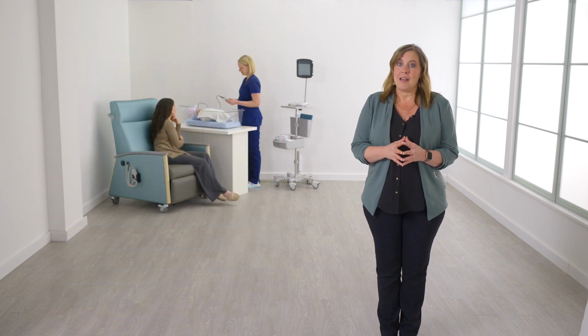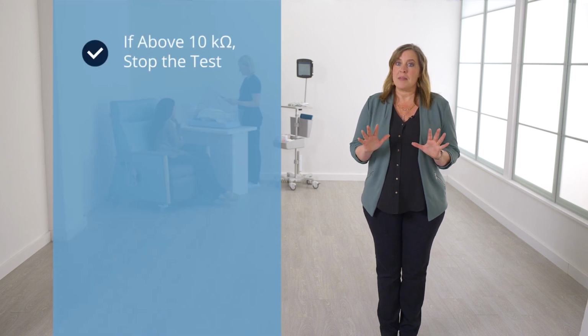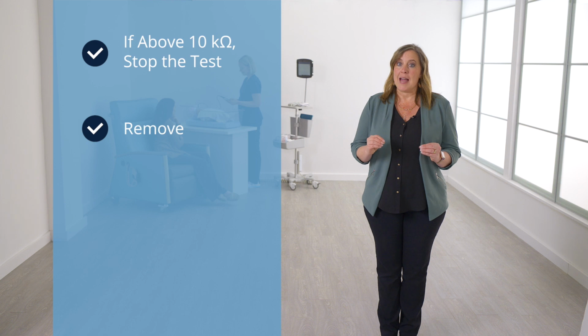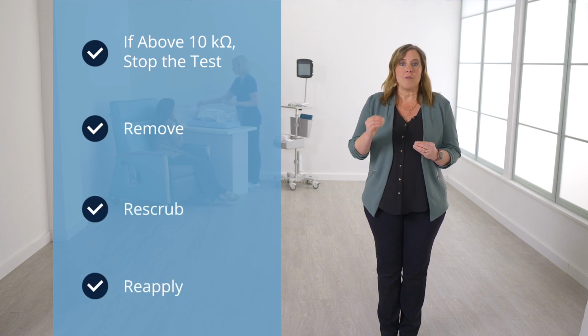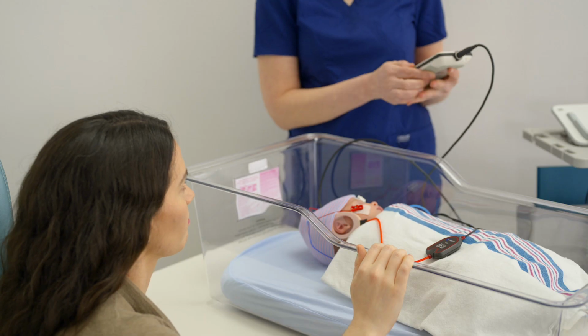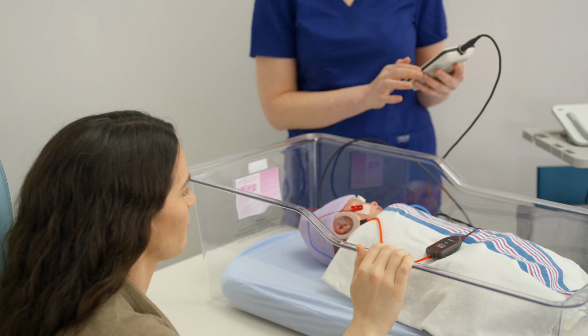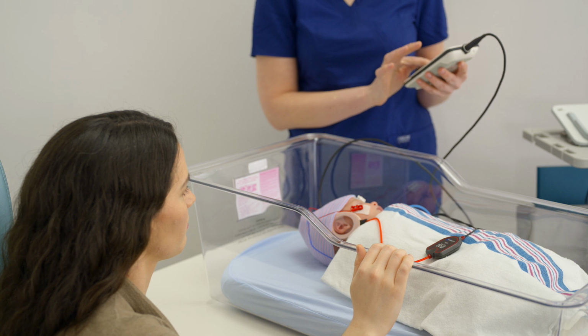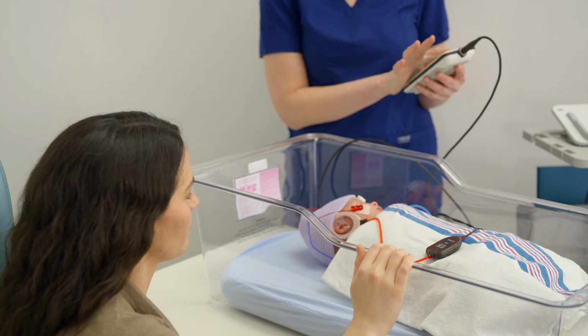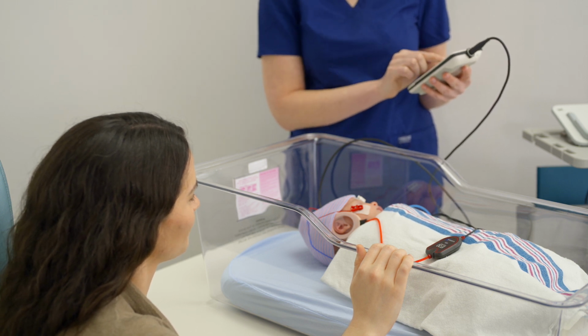It is recommended that the impedance value be 10 kiloohms or lower for all 3 electrodes. If they are not, stop the impedance check, remove the snap electrode corresponding to the high impedance, re-scrub, and reapply the electrode. Retest impedance and proceed with the screening. If impedance is greater than 50 kiloohms at any electrode site, the ABR screening will not begin.